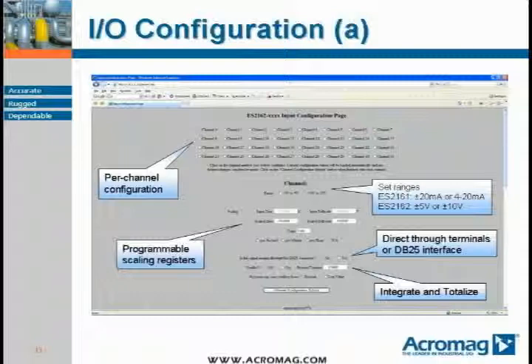Expanding its flexibility, each input port, or 8-channel group, on the EtherStax module can be switched between the DB25 standard connection or direct screw terminals via the web configuration tool. If the DB25 interface is selected for a channel, the unit automatically groups 8 channels through DB25.